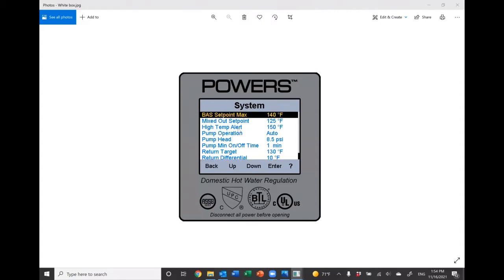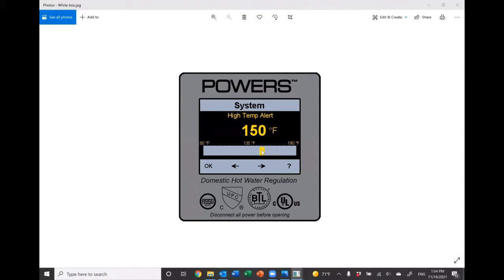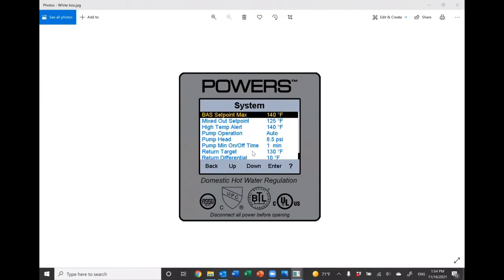You set up your high temp alert, go into high temp. I set it at 150, so let's say I want to set my high temp alert at 140. So I dial that into 140, hit okay. If the outlet temperature was to rise up to 140, this thing would shut down, fail to cold, recalibrate, come back up, try to balance back in. And if it continued to hit that high temp alert 3 times in a row, then it would go into a lockout mode, fail to cold, and it would sound an alarm. Someone would have to come down and troubleshoot, figure out what's going wrong with the system.